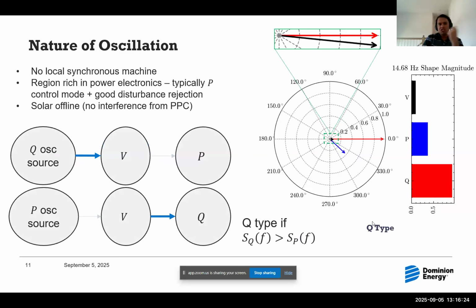Okay, and then for mode shape itself, what is the nature of the oscillation? If you look at the spectrum for reactive power and real power on all the lines in that region, there are no synchronous machines locally in that part of the system. So essentially, the way the PV plant controllers are designed is that there's a pretty good decoupling between P and Q. So in the past, when we have had any oscillations in solar plants, if an oscillation comes in reactive power, it's a volt-var type of oscillation.